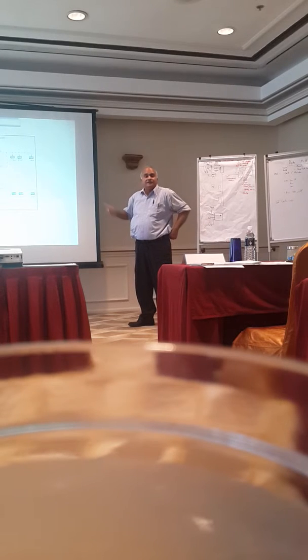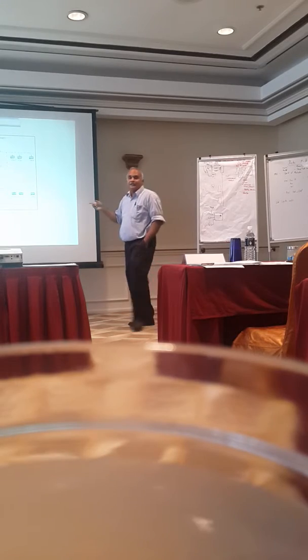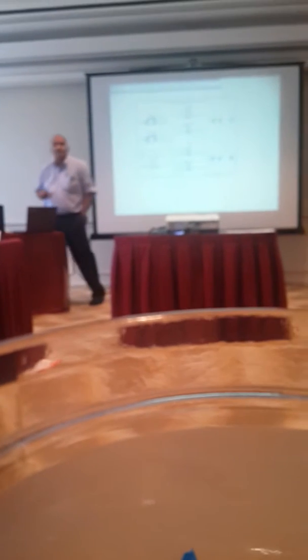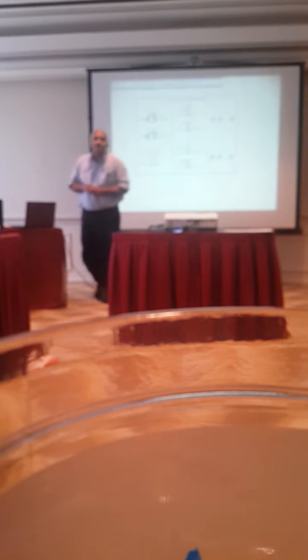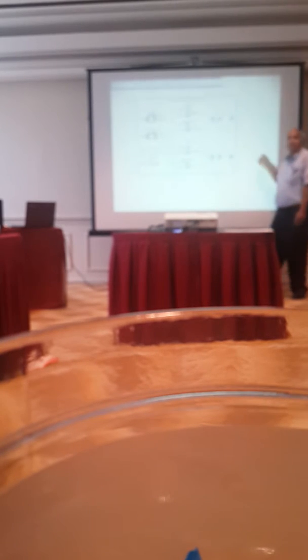This company - you all remember this company? This is Astro. Astro floated a tender last time, and they wanted redundancy in the field level controller. That means not just the primary and master on the main DDCs - they wanted redundancy there too. They said because your field controller connects to all the terminals and other controllers, if this controller goes down, this whole string of controllers will lose communication. So they said, no, I want field level redundancy. This was the architecture we proposed at that time.